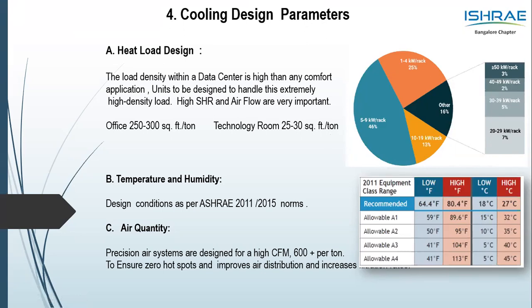These cooling units which go into the server room have an SHR. What is SHR? It is the sensible heat ratio, which is sensible cooling divided by the total cooling. Total cooling would be sensible plus latent, close to 0.9 to 0.99, whereas any comfort AC would fall under the bracket of 0.6 to 0.7 because they cater more to the latent load in a comfort application.